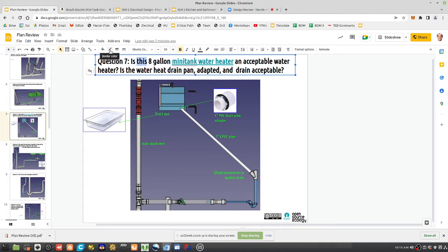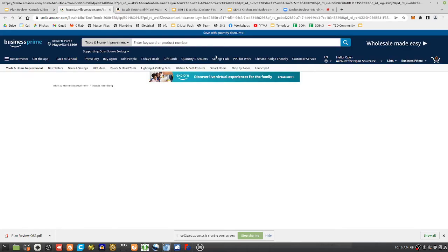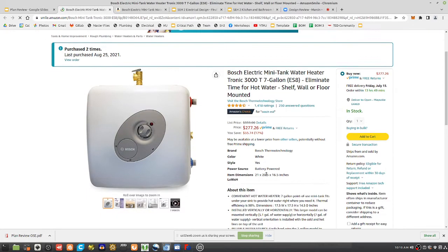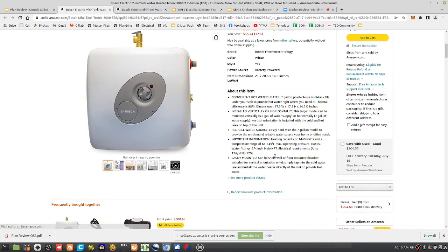And so, what is that heater preset? What's the temperature? Is it like 120 degrees or probably less? I think you can preset it to wherever. Standard is whatever the standard is. I'm not sure. They preset them to like 120 or so that someone doesn't get burned. Range is 65 to 145 max. And I think they come with preset at 120.